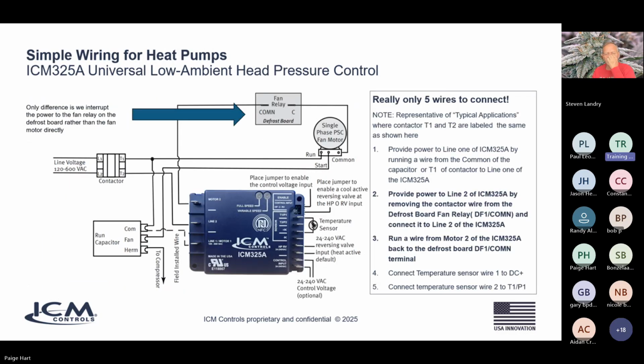So the next diagram will show you how we do the same thing, only it's a little bit different wiring when it comes to heat pumps. All right. Now, when we talk about heat pumps, remember heat pumps got a defrost board, and a defrost board needs to be able to shut off that fan motor when you go into the defrost cycle, but yet bypass the ICM control when it wants to be in heat mode. So with a defrost board, we have to accommodate for 2 things. We have to accommodate for when the unit goes into the heat mode and we want to bypass our control. And we also have to accommodate for the defrost board when it wants to shut the fan off during the defrost cycle. We only want our control to be in play during the cooling mode.